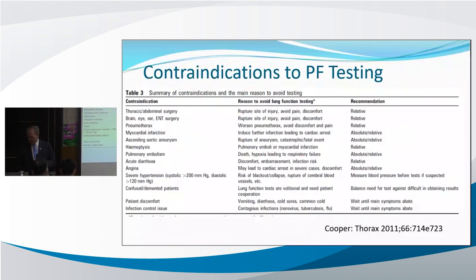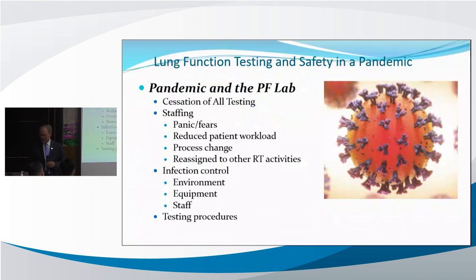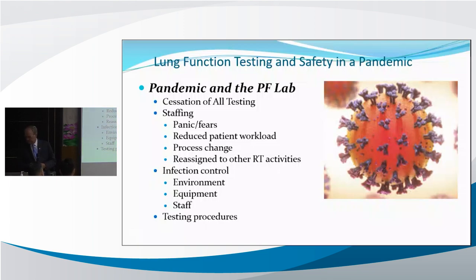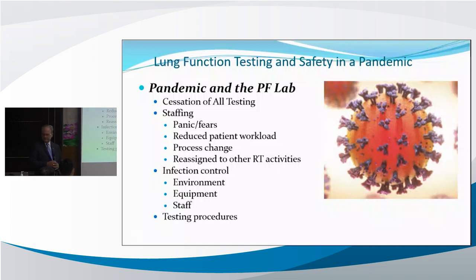One more comment relates to the pandemic. When the pandemic hit, spirometry and all lung function testing was initially stopped because of the aerosol generated when performing the maneuver. Probably the biggest lesson we learned from this is that using a bacterial filter on a spirometer is really an essential component of that spirometer equipment.